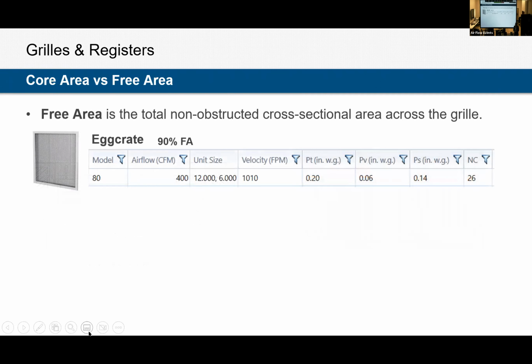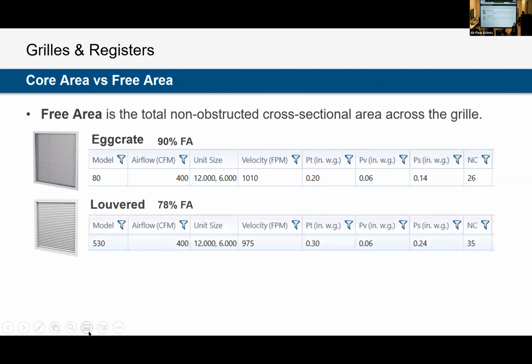What does that do for our performance? So free area, again, is our non-obstructed path for air to come out of. If we start with something like an egg crate, this is a pretty large and open grill. We've got 90% free area, so we're only obstructing 10% of the full nominal size. If we compare that to a louvered grill, you're down at 78% free area. But let's look at some of the performance metrics. Our pressure is going up, so we can see our static pressure is up 1/10 of an inch. And so is our total pressure. NC is also up 9 NC. So by reducing, what is that, 12% free area, we're adding a good bit of sound and pressure drop.